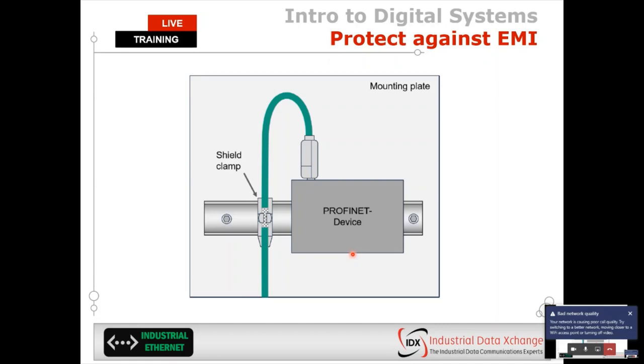Sometimes that's not good enough. It's often even better practice to strip away some of the outer covering of the cable as it enters and exits panels, and actually ground the shielding so that any noise, EMI, electrostatic or magnetic interference picked up in the field drains to this point before it actually gets to the device.